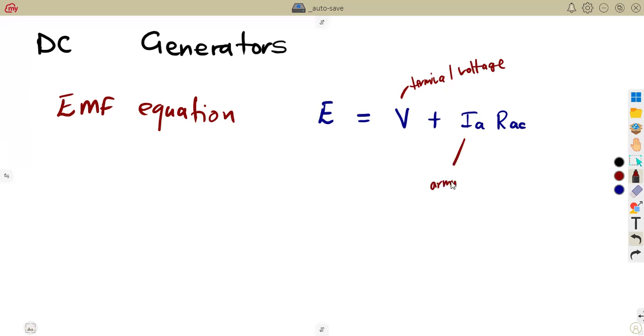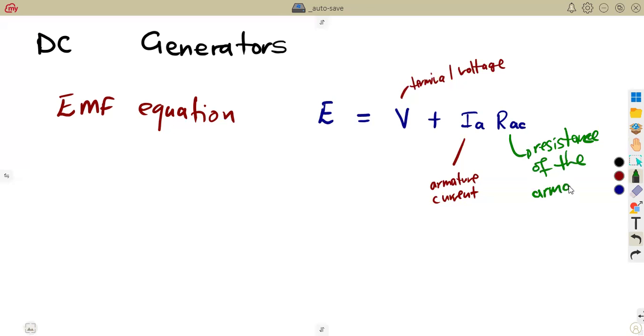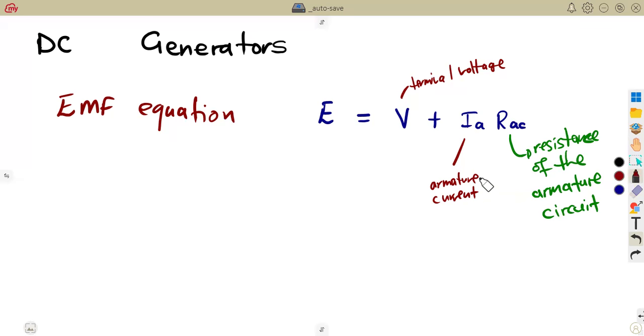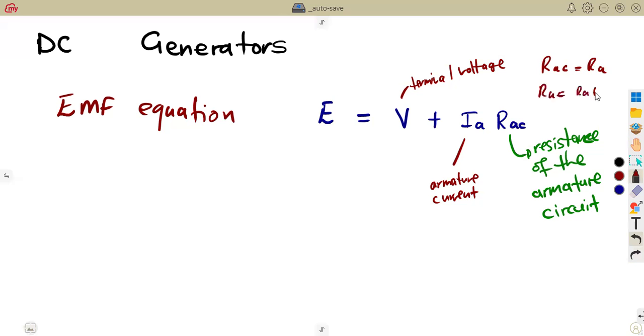We're not talking about the diagram here — we'll talk about the diagram later. This Rac represents the resistance of the armature circuit. I'm saying the resistance of the armature circuit, not just the resistance of the armature. If I want to refer to just the armature resistance, I refer to it as Ra. The armature circuit resistance is the total resistance where the armature current flows. It can equal just Ra, depending on the circuit — for example, if there is a series field present.